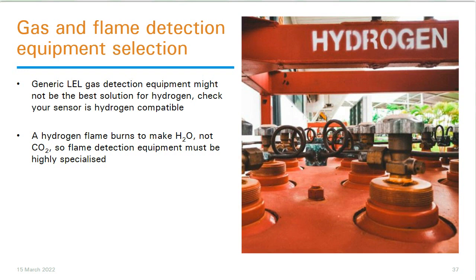So we might say, oh, well, listen, I've got methane here, and methane is a flammable gas. Now I'm using hydrogen. My existing system should be okay. Well, maybe it's okay, but please don't make that assumption. Please validate that any changes in the flammable gases that you're processing, such as the introduction of hydrogen, will continue to be valid for your existing systems.